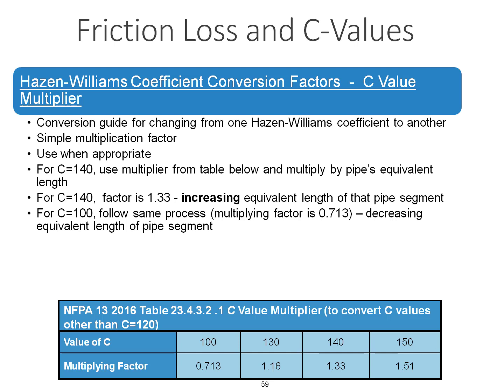Table 23.4.3.2.1 is the C-value multiplier to convert C-values other than C equals 120. For example, C equals 140, the factor is 1.33, increasing the equivalent length of that pipe segment.